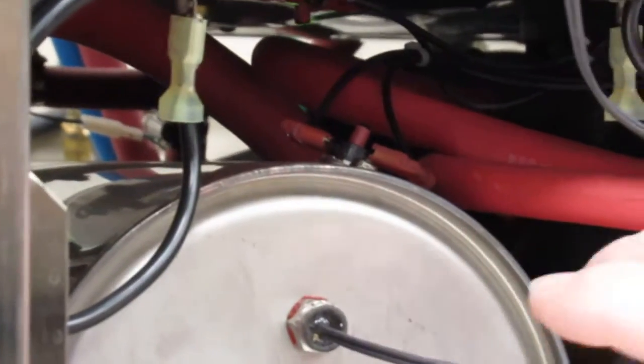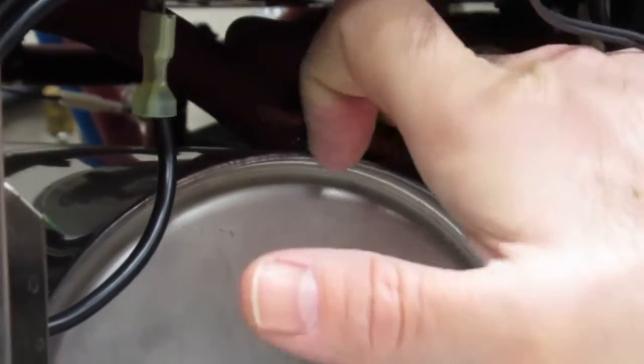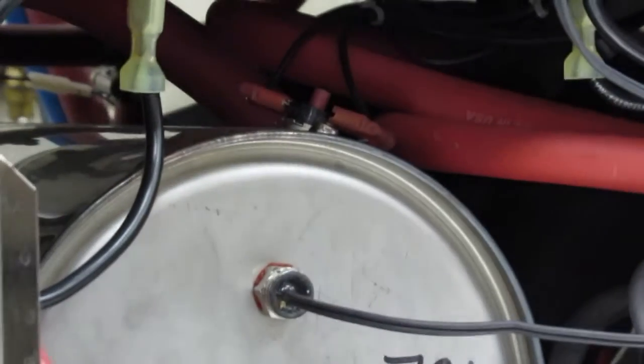If you have a problem where your booster tank is not heating, on top of the booster tank is a high limit. It's just a red push button, push it down, and if it clicks, then it resets.